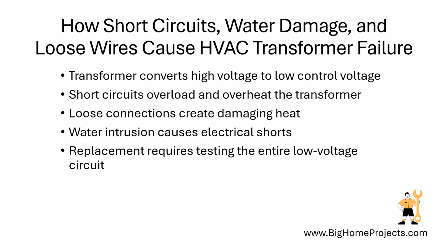One important detail is that replacing only the transformer may not fix the problem, because the original short circuit can burn out the new one almost immediately. Before installing a replacement, a technician should inspect the wiring, test connected components, check the fuse, and confirm that the transformer has the correct voltage and power rating.